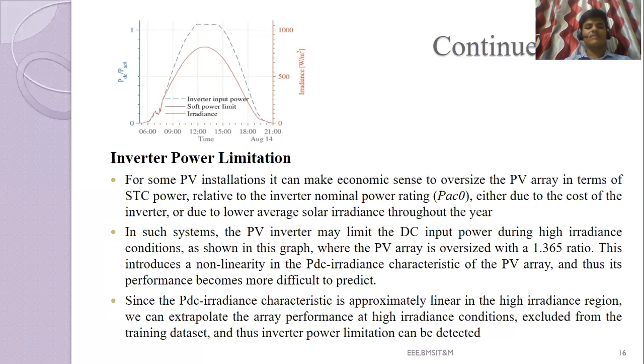In some areas, we have low solar irradiance throughout the year, where the weather conditions are not completely suitable for solar charging. In such cases, we increase the size of the PV array in order to capture more solar irradiance. In such systems, the PV inverter may limit the DC input power during high irradiance conditions, as shown in this graph, where the PV array is oversized with a 1.365 ratio. This introduces a non-linearity in the PDC irradiance characteristics of the PV array, and thus its performance becomes more difficult to predict.